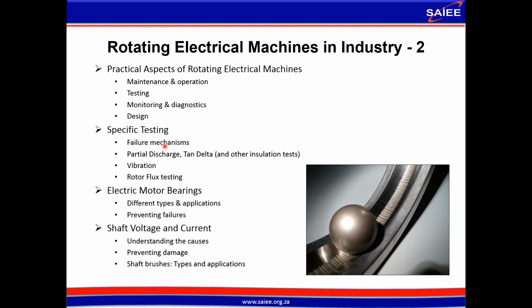Then we look at specific testing. I already mentioned partial discharge. Look at tan delta, the difference between the two and where both are headed. Vibration, I've mentioned, and then rotor flux testing. This is a method of detecting interturn faults on synchronous machines. It's becoming more and more common, and it's extremely accurate on certain types of machines and very well worth knowing about and understanding.